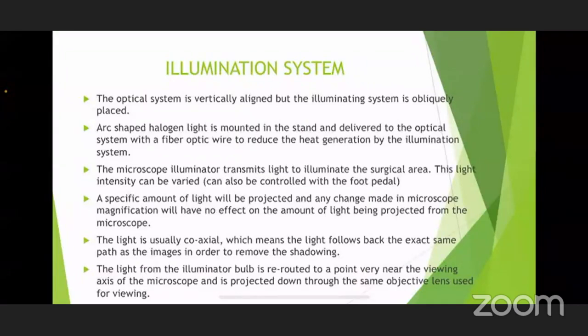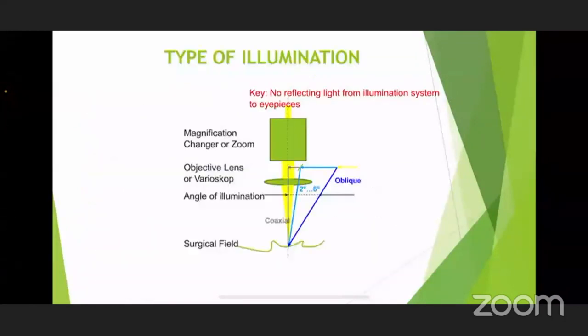One important thing regarding the illumination system: we use a coaxial method of illumination. The purpose of coaxial illumination is that the light follows back the same path as the images, and this helps us in avoiding shadowing. This is an important concept used in ophthalmic operating microscopes.